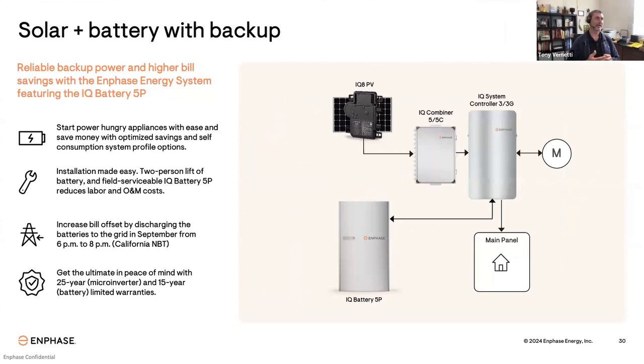And of course, we have our battery backup system. Pictured here is a typical whole home backup where you've got the main panel that's supplied by the system controller 3 or 3G. And you've got your IQ8 PV system on the solar array connected into the IQ combiner, and an IQ battery 5P, as many as are needed for this particular customer.